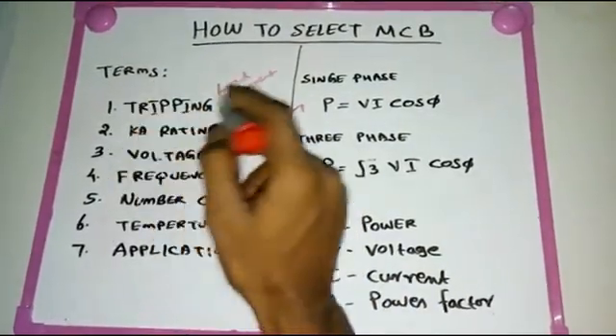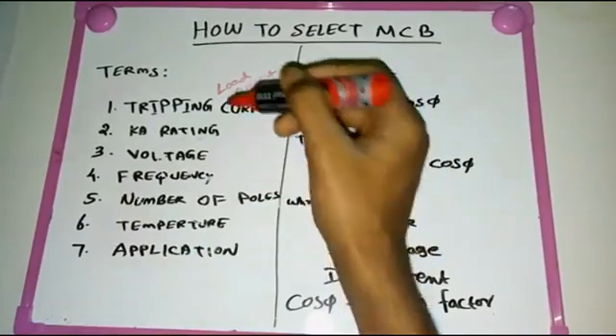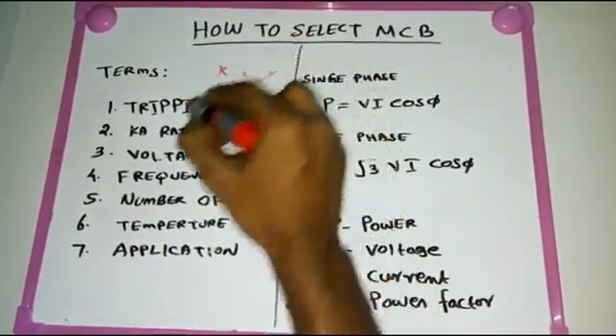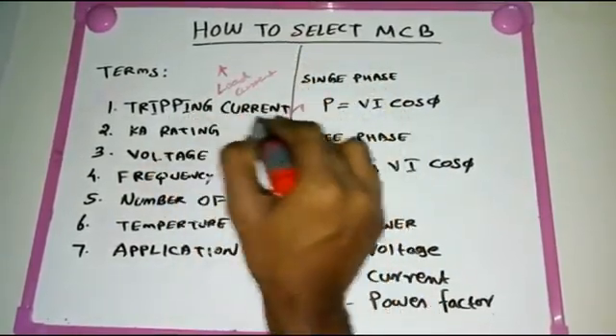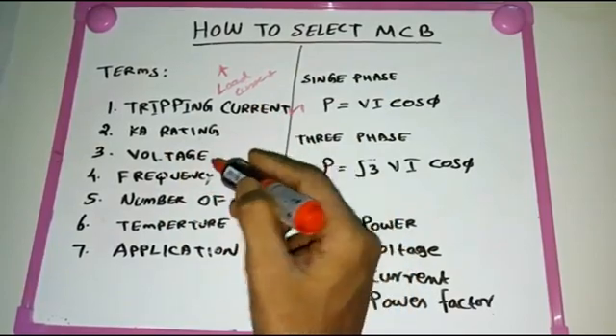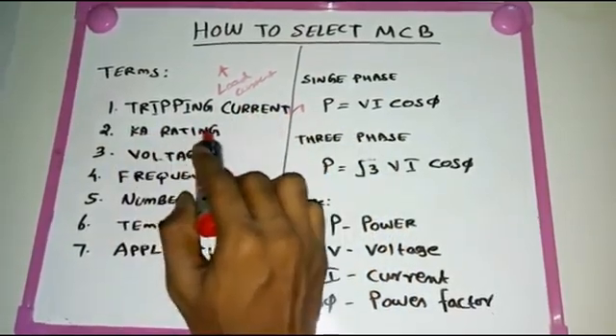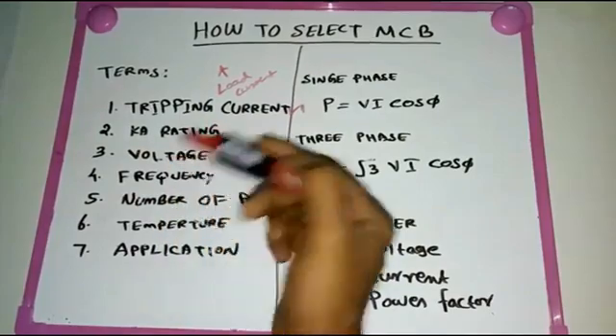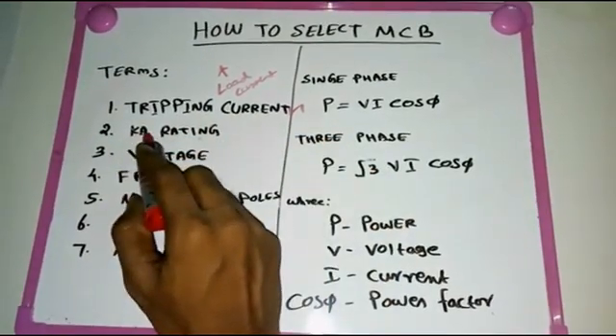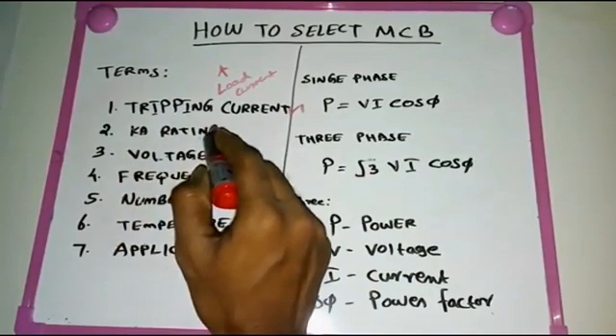We select the tripping current such that the load current represents 80% of it. That means if you have 80% load current, you select for 100% tripping current. For example, if load current is 80 ampere, you choose a 100 ampere tripping current MCB.